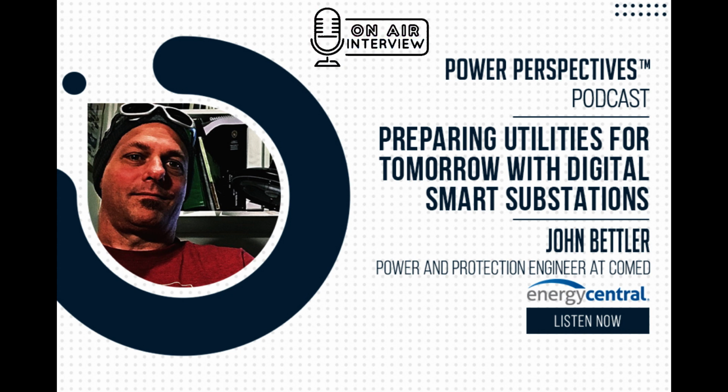Now I put Matt in test mode and then I publish out the trip and I'm in test mode also. Matt now understands what I'm saying and will respond accordingly. Jason, you still are not in test mode, so you ignore what's happening. So it's in this way that I can use this test mode feature to prove my signal from me goes to you, to Matt, and then I'll put Matt not in test mode and put you in test mode, and then I can prove it goes to you.